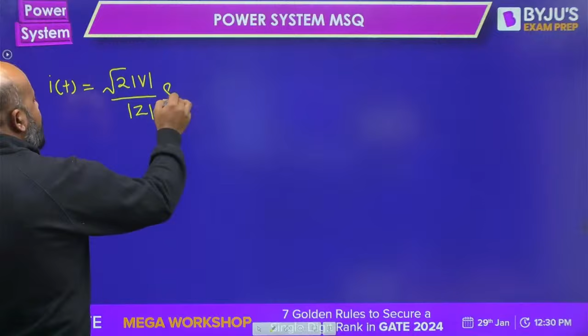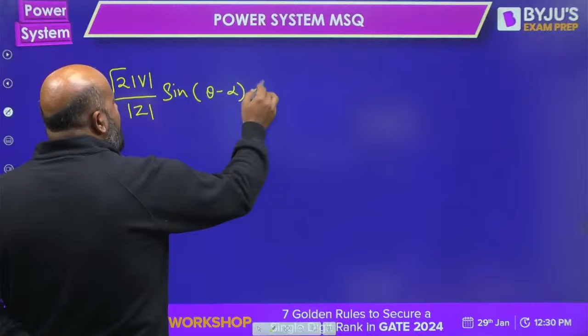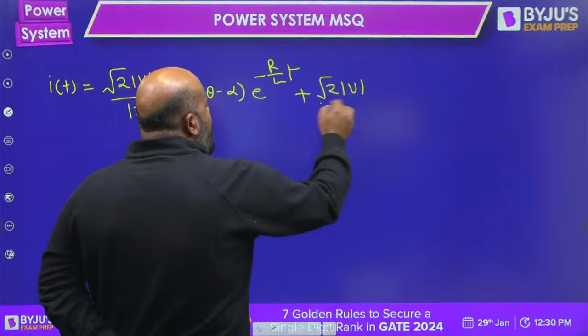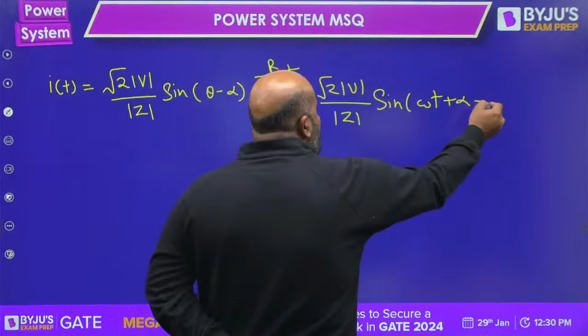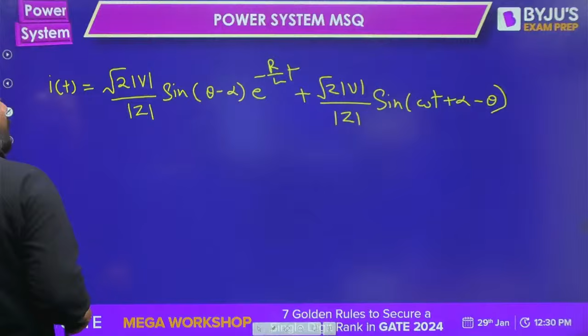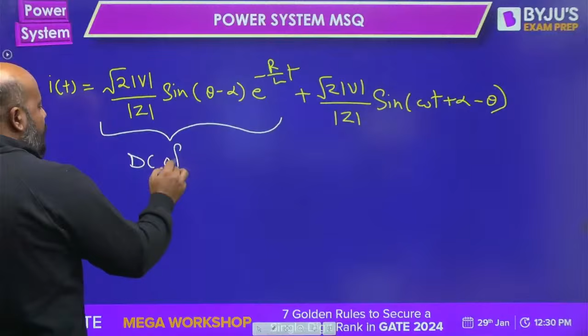It was root 2 mod V mod Z sine theta minus alpha, e raised to the power minus r by L t, plus root 2 mod V upon mod Z sine omega t plus alpha minus theta. This is the current response for a sudden short circuit at the terminal of the alternator when it is at no load. This is the DC offset because of the fault, and this is the symmetrical short circuit current.